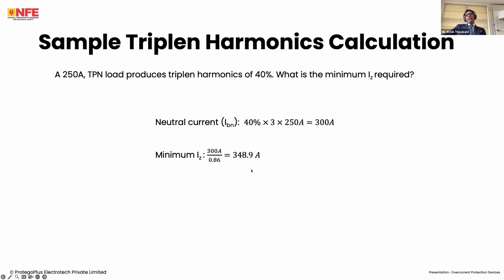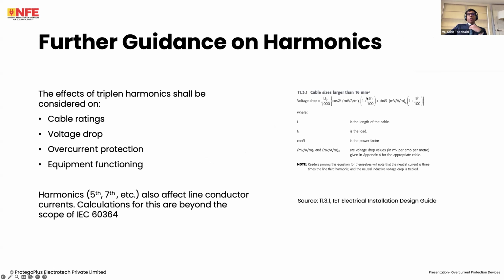So our IB value, the design current on which the IN and the IZ value selected, becomes 348.9 amps. Further calculations: harmonics not only affect current carrying capacity, but even voltage drop. So this is just an example. Again, I'm not going to go into too much detail because we want to keep things simple. My job is not to teach you how to do electrical calculations, but just to give you a picture of what you have to consider.